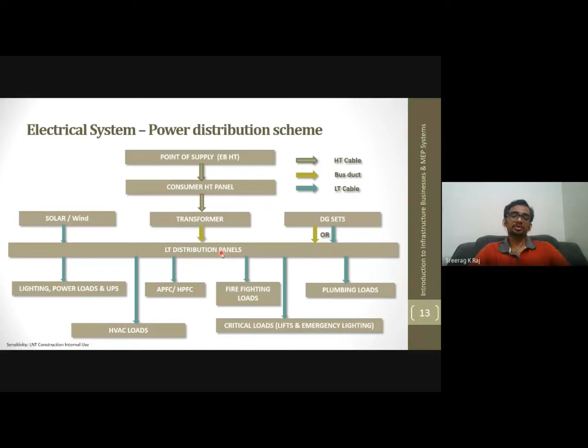Normally from HT, this is the HT cable, and from the transformer to LT distribution, the current value will be very high. So we cannot have multiple runs of cables. For that purpose, we use bus ducts. A bus duct is nothing but a big thick conductor in a rectangular shape to carry current from the transformer; for high current distribution, we use this bus duct.